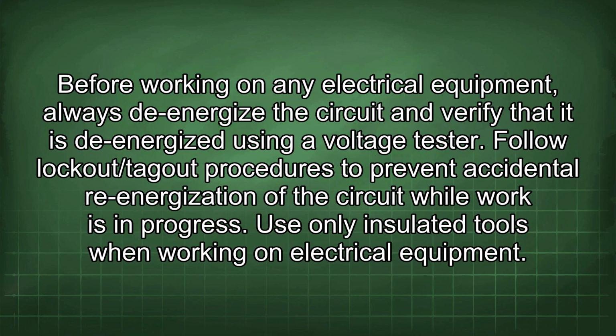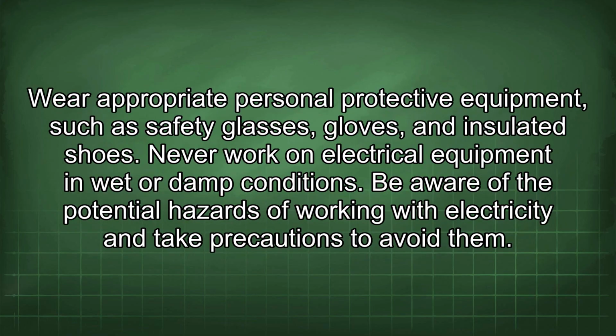Before working on any electrical equipment, always de-energize the circuit and verify that it is de-energized using a voltage tester. Follow lockout/tagout procedures to prevent accidental re-energization of the circuit while work is in progress. Use only insulated tools when working on electrical equipment. Wear appropriate personal protective equipment such as safety glasses, gloves, and insulated shoes.